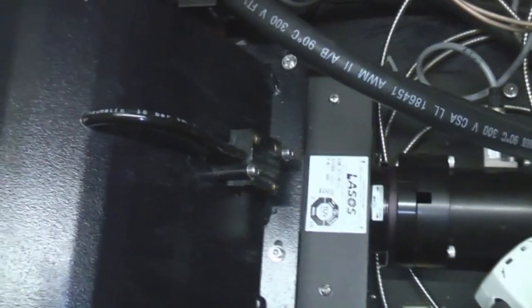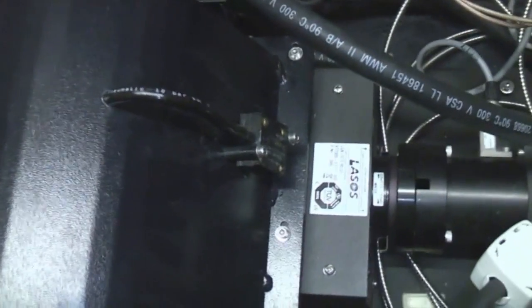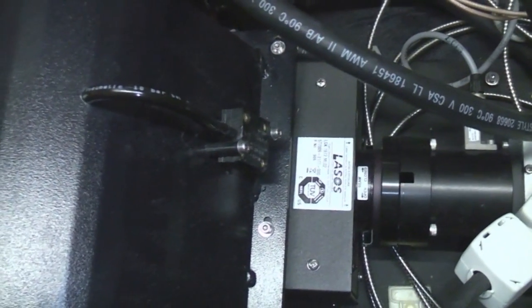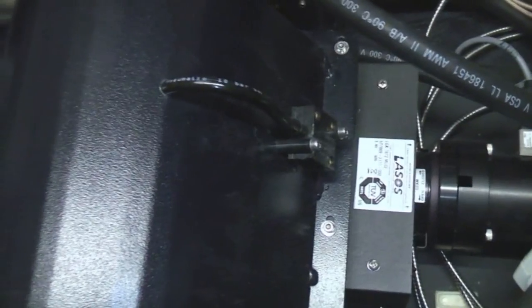There's also a fairly high current filament and a high voltage igniter inside the Argon laser, needed to strike it. Once struck, the running voltage is around 100 to 200 volts, and you adjust the output power by adjusting the beam current.